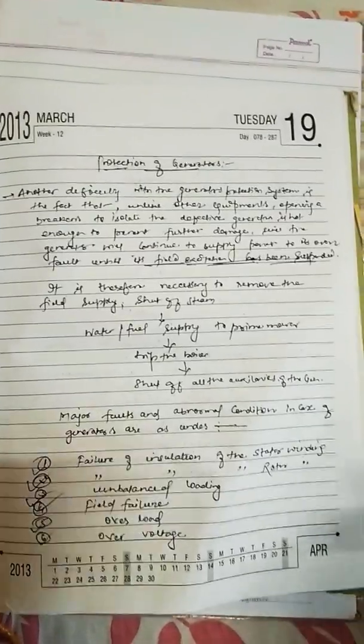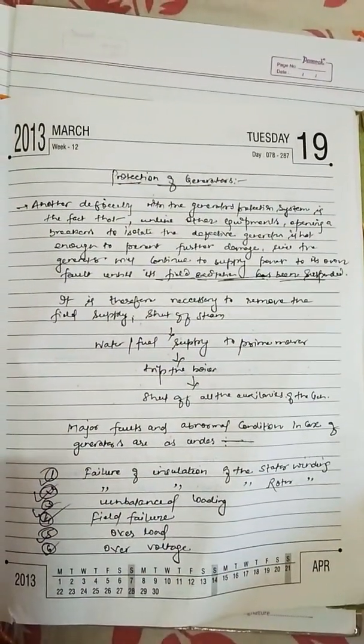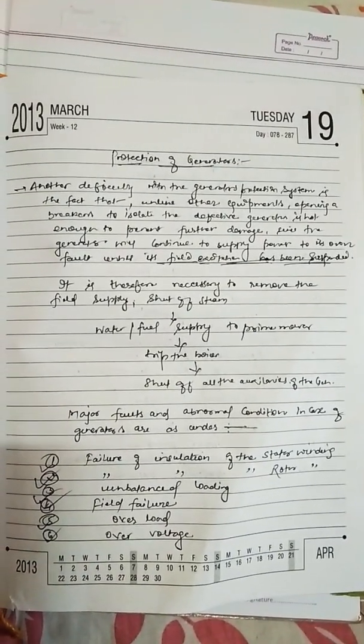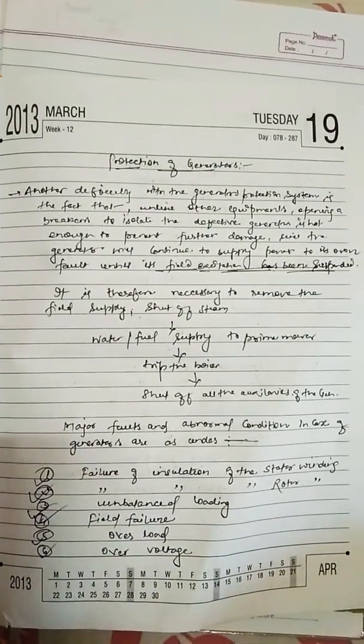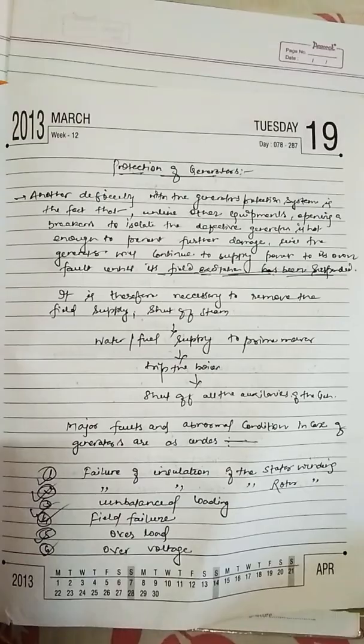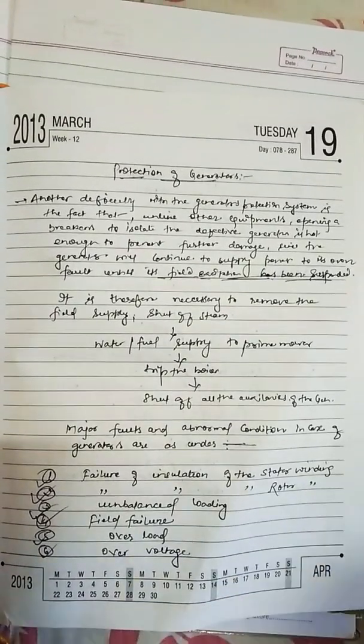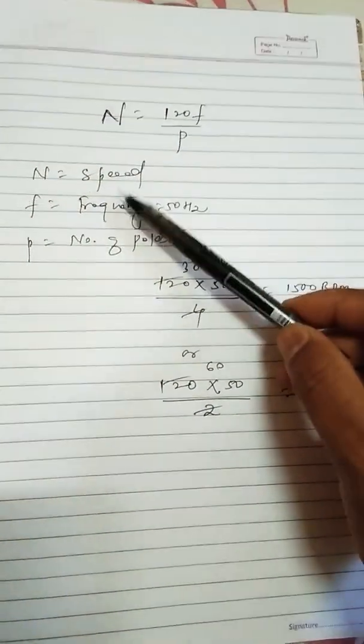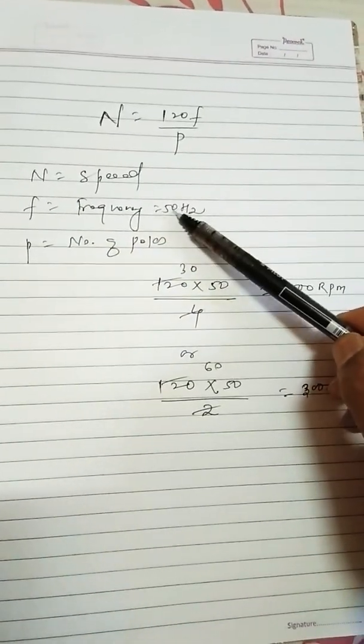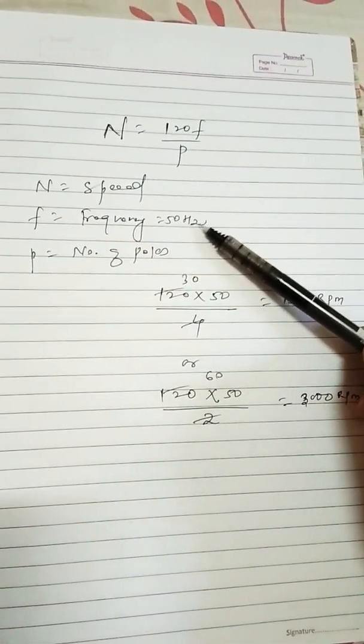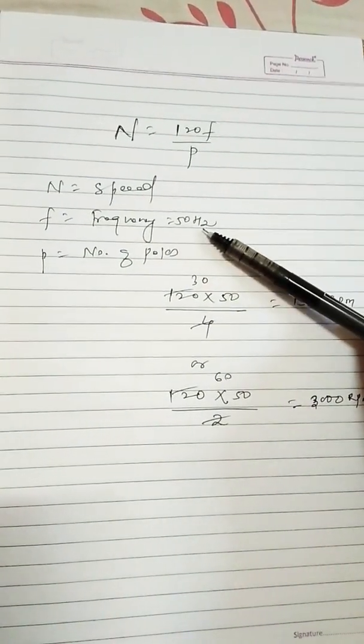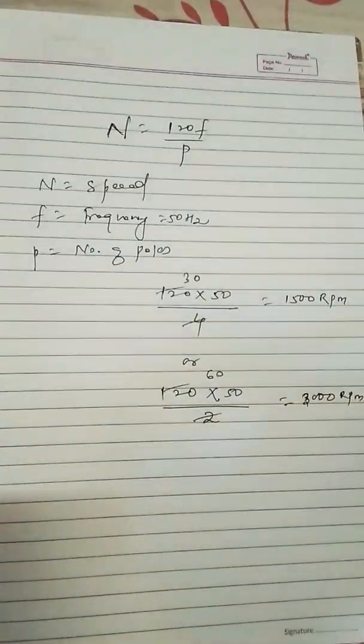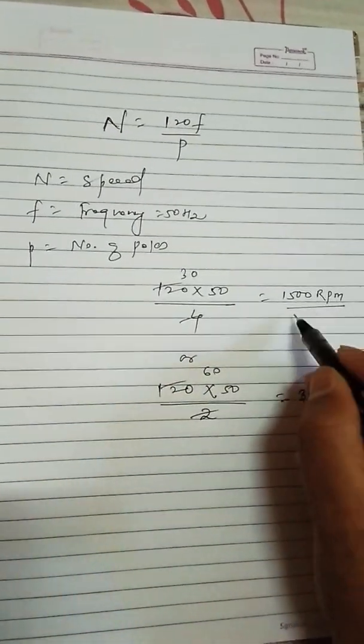Let me start with the basics of what happens inside a power generation or captive power plant. The turbine rotates with the help of steam or gas and is connected with a shaft. When the turbine reaches its RPM — either 1500 or 3000 RPM — we use the basic formula: n = 120F / P, where n is the speed, F is the frequency (50 Hz in India, 60 Hz in America), and P is the number of poles.